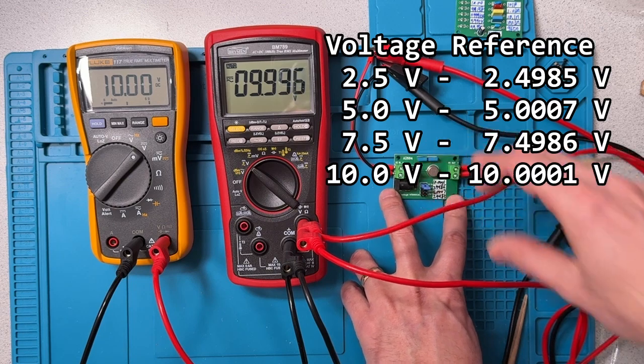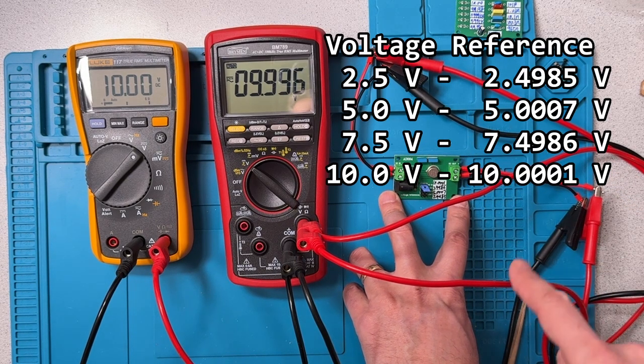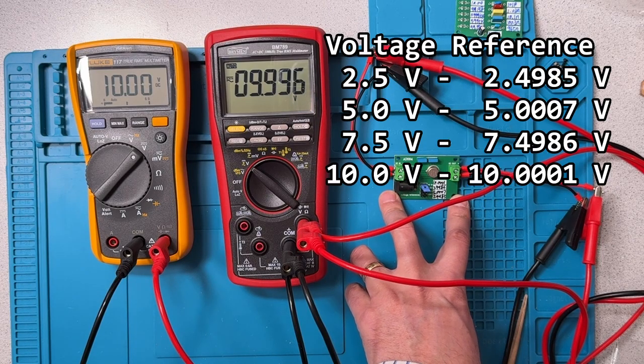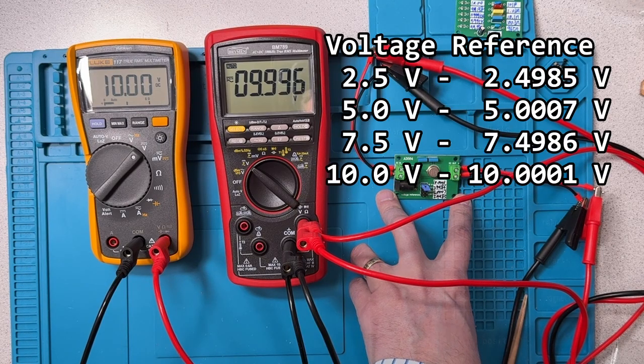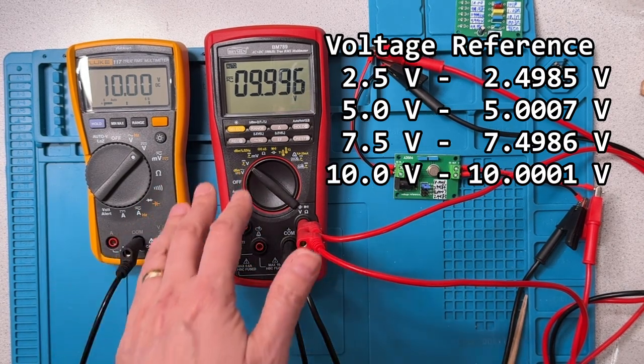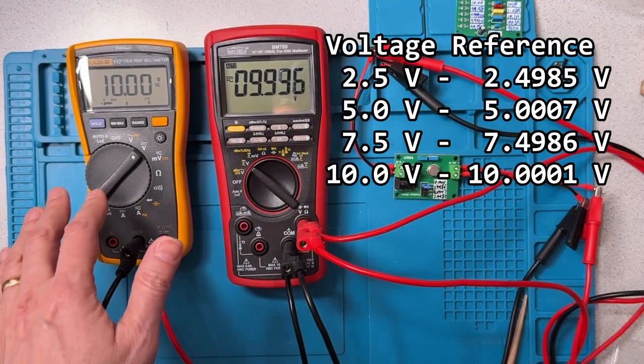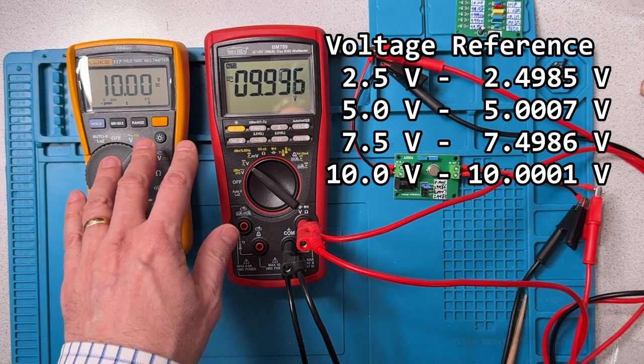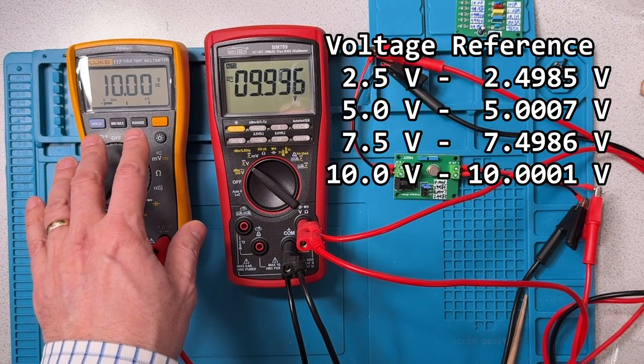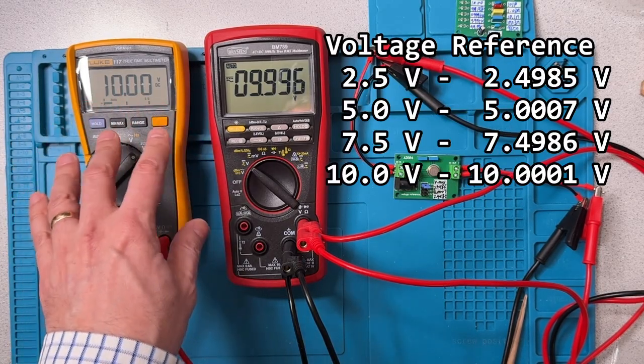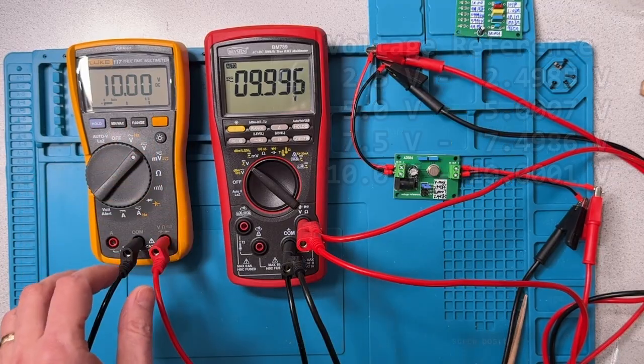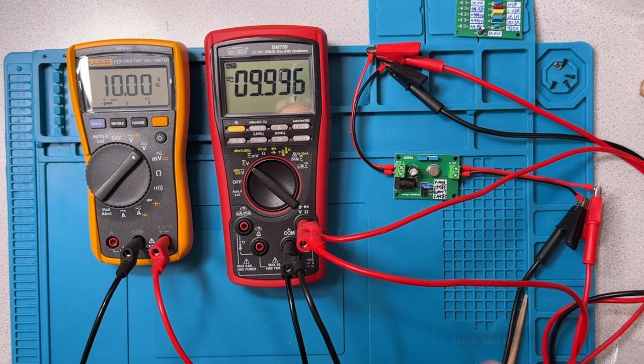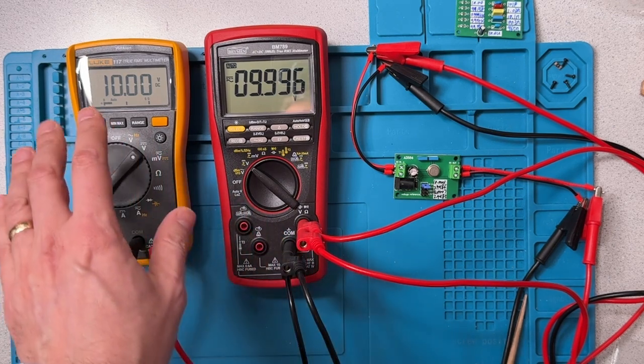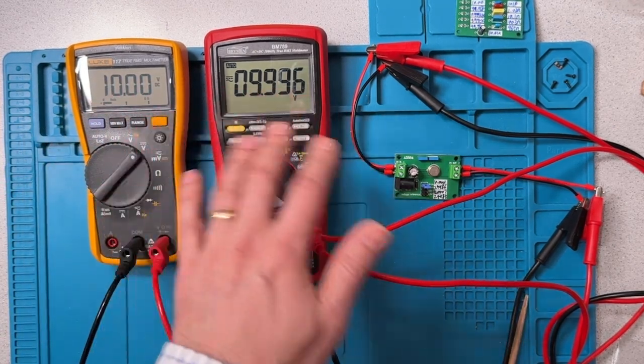Now we're going to go up to 10 volts, and the Fluke is showing exactly 10 volts. The calibration reference here shows 10.0001. The Brymen here is off by about 4 millivolts, whereas on the Fluke, we can't really tell. It could be off by the same amount. It could be more accurate. We can't really tell because we don't have the same number of digits of precision on the Fluke. 3 out of 4, certainly we've seen the case that the Brymen is more accurate, and in the fourth, hard to tell just because of the rounding that might be taking place.